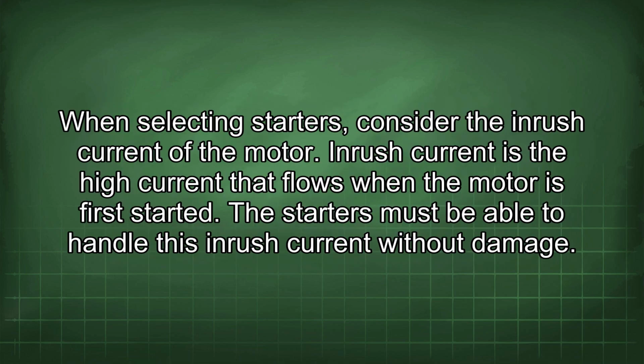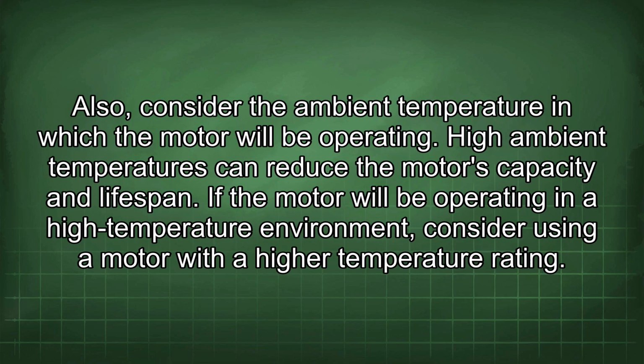When selecting starters, consider the inrush current of the motor. Inrush current is the high current that flows when the motor is first started. The starters must be able to handle this inrush current without damage. Also, consider the ambient temperature in which the motor will be operating. High ambient temperatures can reduce the motor's capacity and lifespan. If the motor will be operating in a high temperature environment, consider using a motor with a high temperature rating.